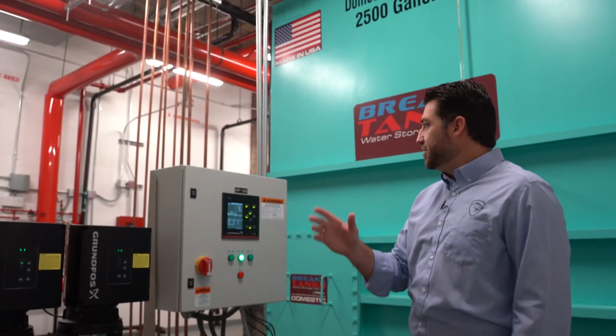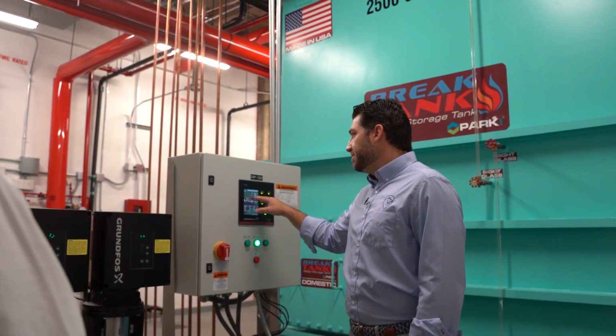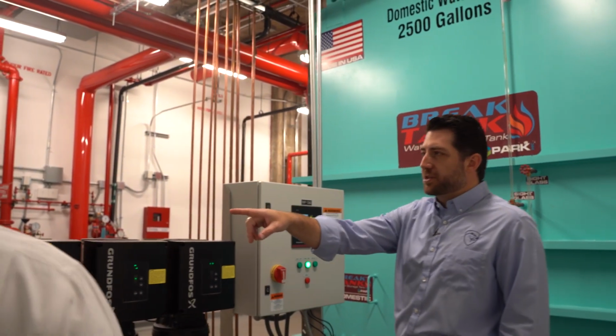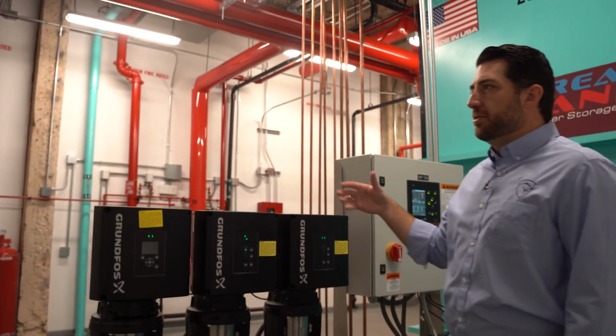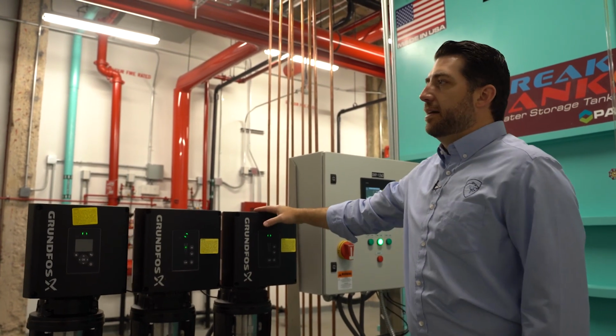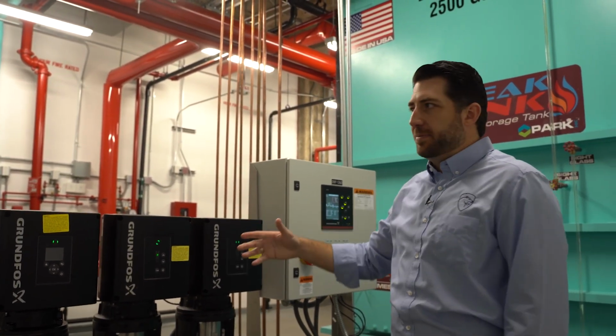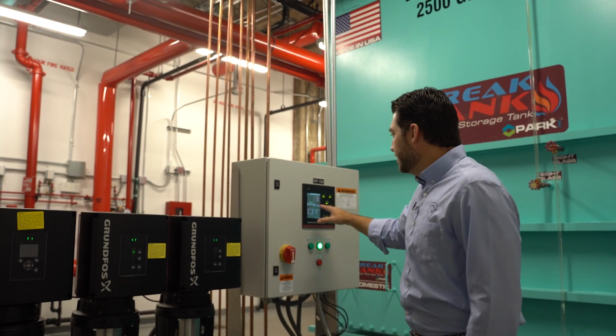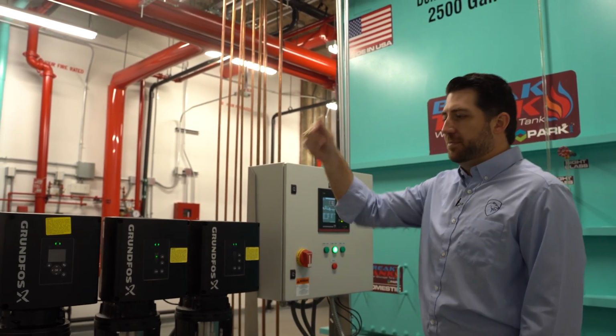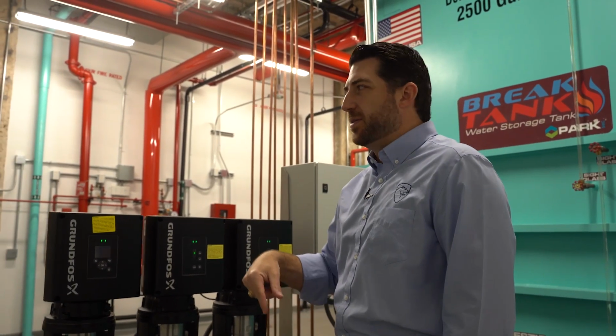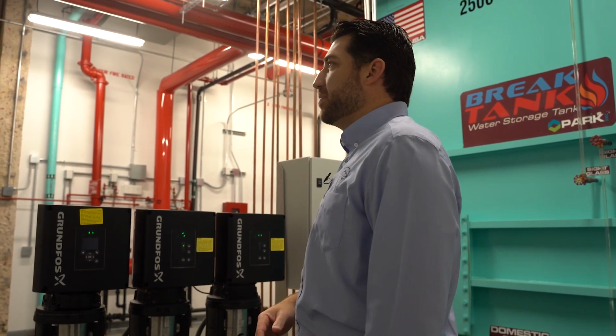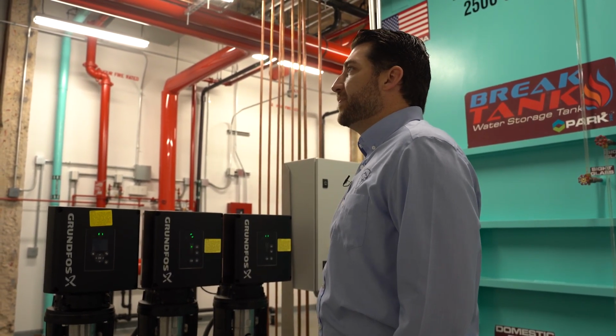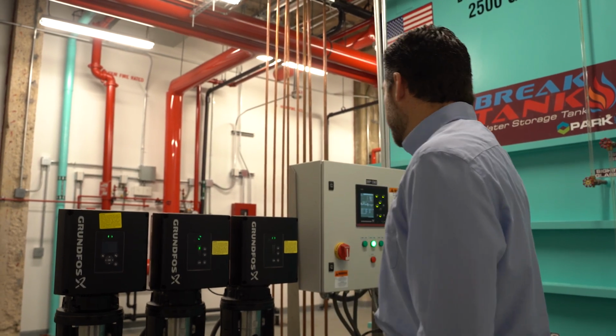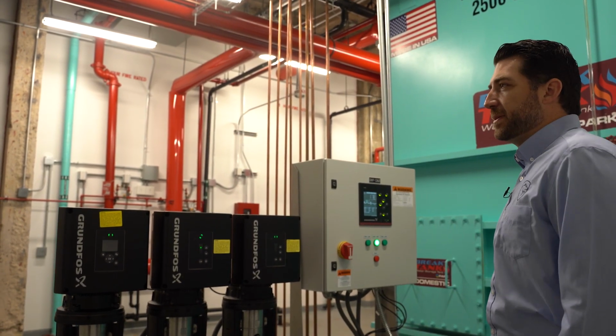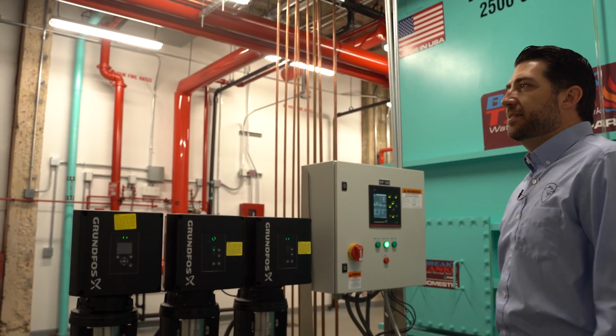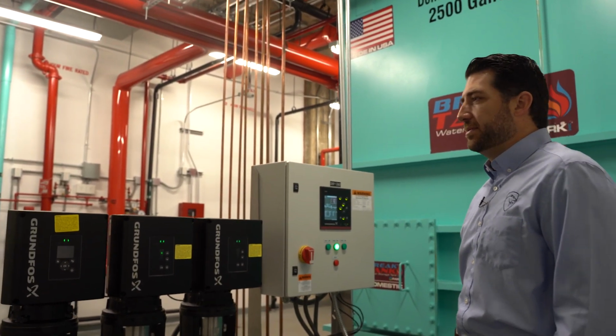It's really interesting that our set point is just shy of 70 psi, but we do have a pressure reducing valve station. Typically you're trying to avoid having any pressure in the system over 80 psi, so if we're only generating 70 psi, why would we need a PRV station? But as you said, it's feeding the basement, so as we go down in the building we're going to have an increase in pressure. So it was interesting to have a PRV station when our booster pressure was less than 80 - don't typically see that, but going down into the basement can build more pressure, so cool to see.